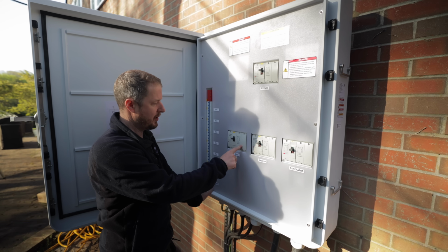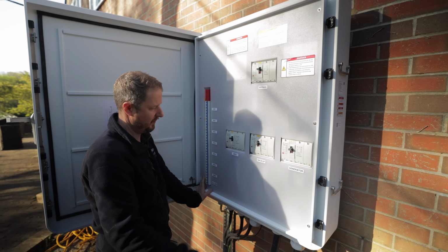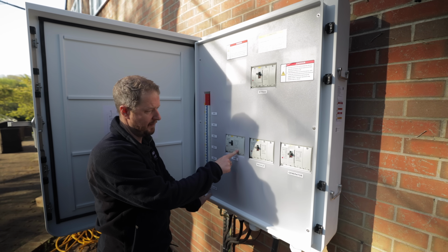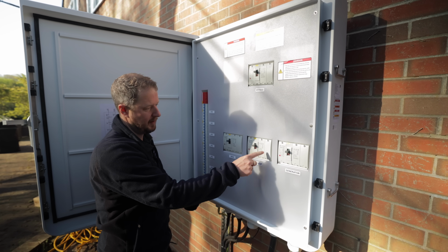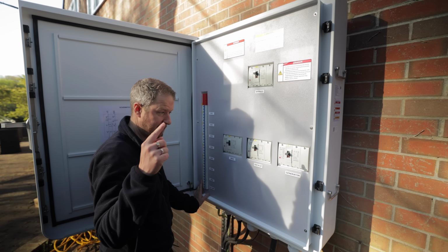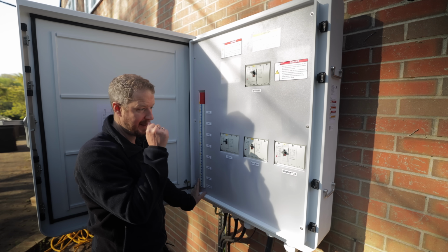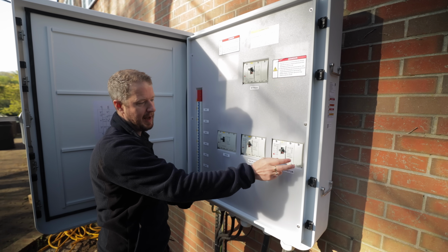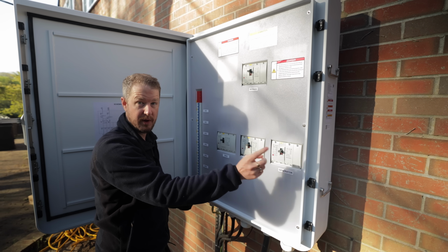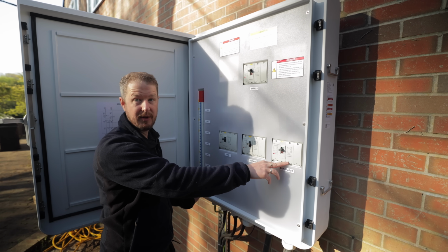How it works: you've got a 250 amp MCCB here, so the grid connection comes in there. Then the backup MCCB feeds all of the power going into the house. You've got a smart port here for your generator, so you can connect a generator to the system as well.